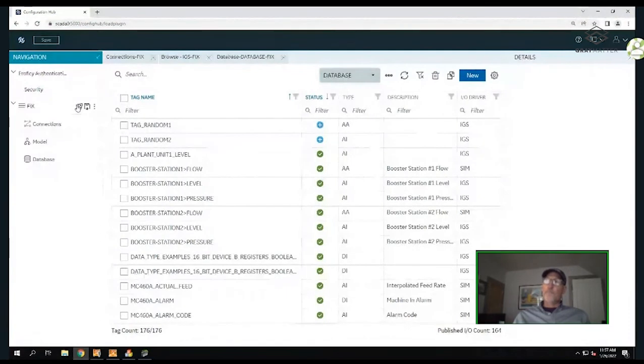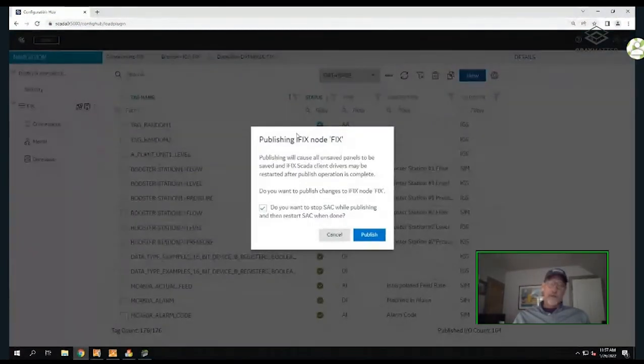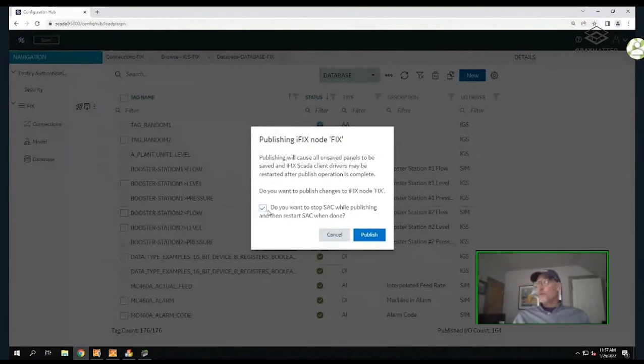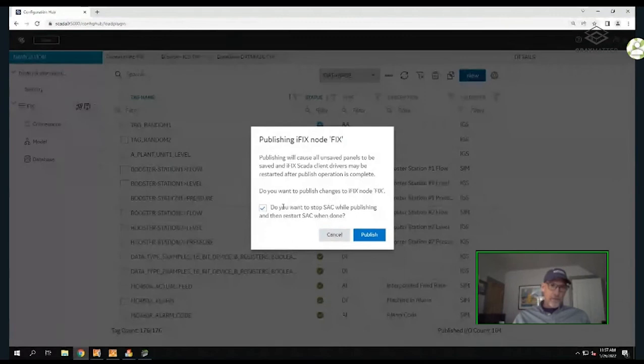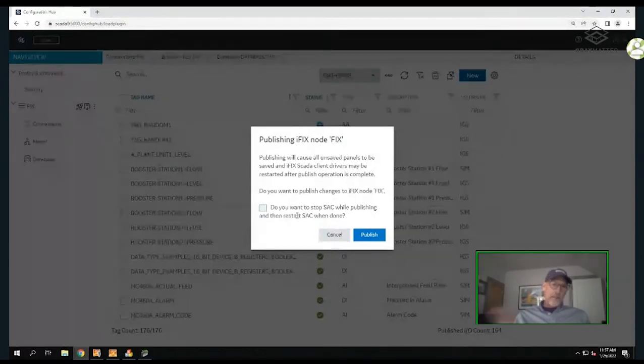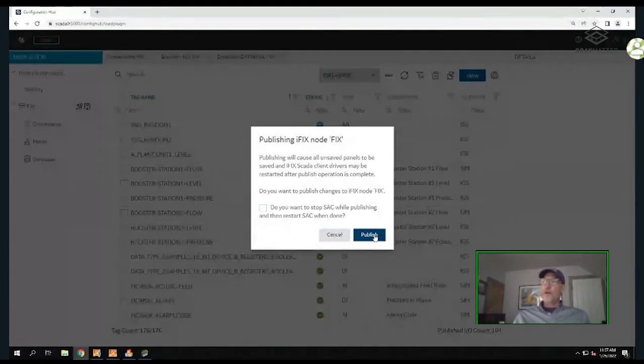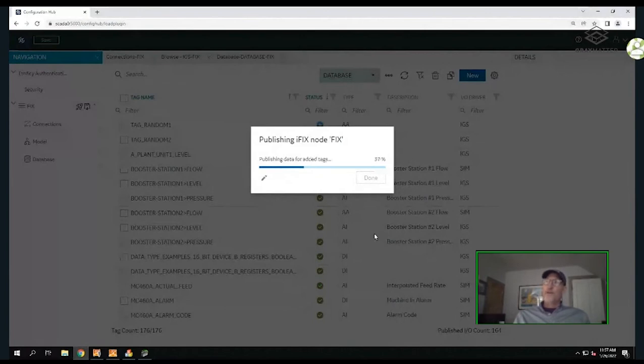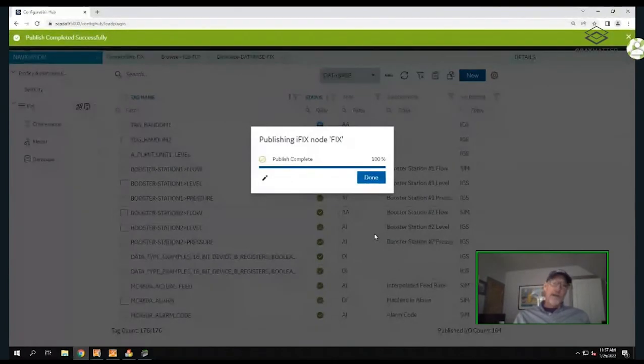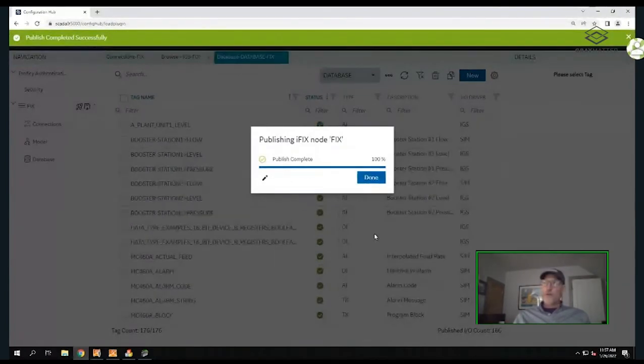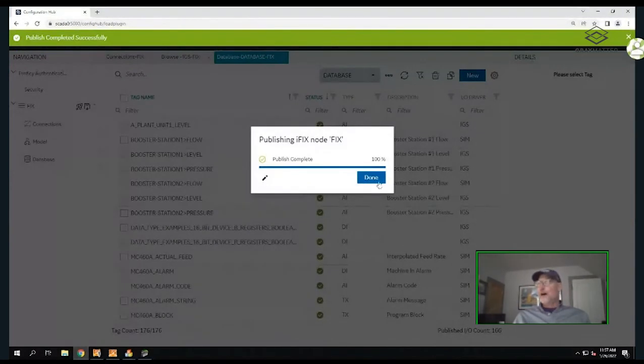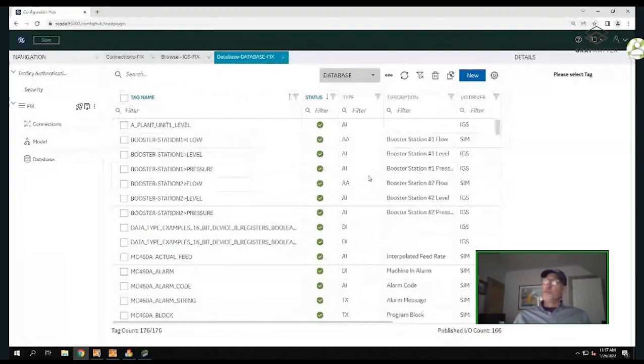I'll go ahead and publish, which brings up the publish window. It asks: do I want to publish the database, and do I want to stop the SAC process - that's our Scan Alarm process, which would stop the database temporarily. I'm not going to do that. I'm going to publish live and not bump my system, so I'll uncheck that and just hit publish. That takes my tag configuration from this web environment into the running system without affecting the status of the iFIX database.